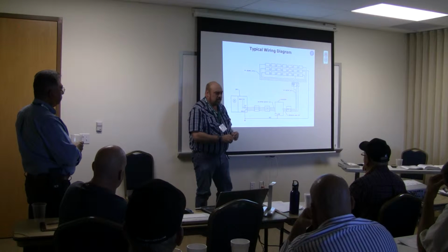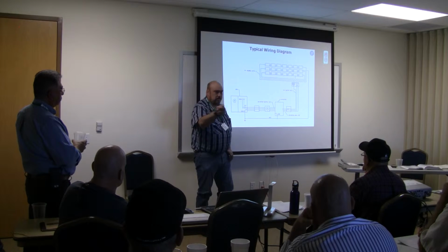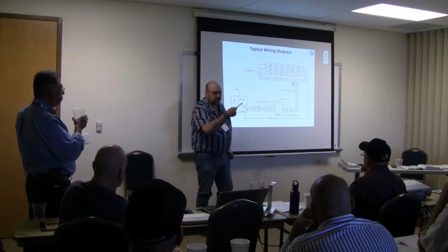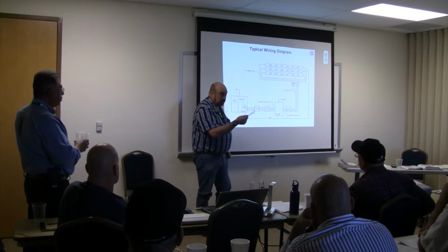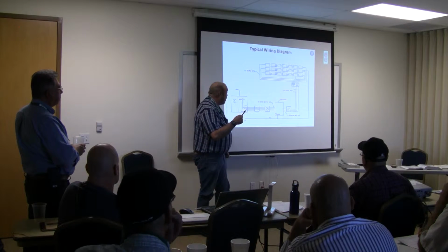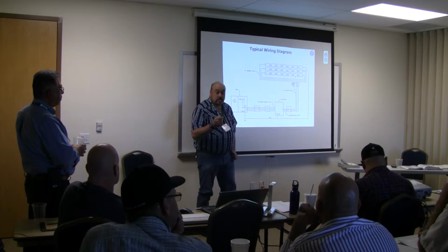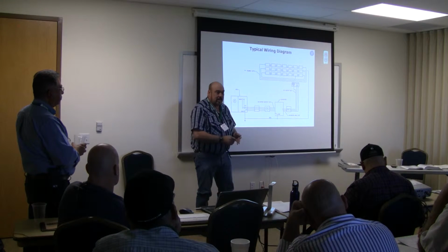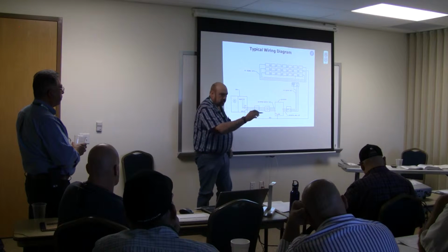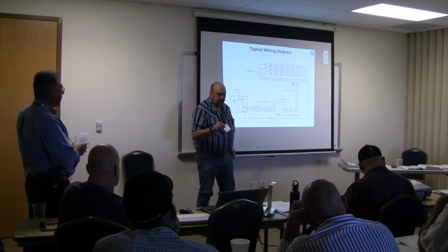That table is kind of a generic table, but it's going to be for, I'm sure there's people here from all over the state. So you're going to go with, we talked a little bit earlier about your lowest ambient temperature ever recorded in that area. That is going to be your correction factor that's going to be in table 690.7.